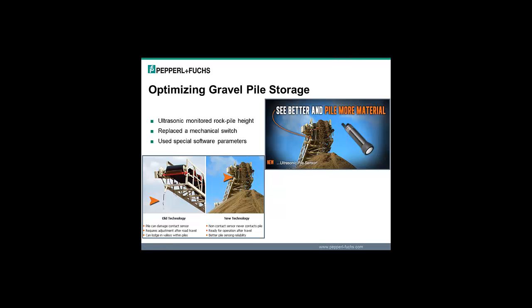Well, this is kind of a neat application for an ultrasonic, and this is for a company that makes conveyors that fill giant yards with piles of gravel and crushed asphalt and things like that. And they had originally used a limit switch, a mechanical sensor that hung from the top of the belt. But that sensor got hit with rocks, it stuck, it broke. It was a pretty violent application. So they decided to try a UC4000 ultrasonic sensor, which gave them about 15 feet of sensing range that they required. And it was able to look at this gravel, we mentioned before, hard stuff, gravel, things like that are great targets for ultrasonics. And this sensor worked great.